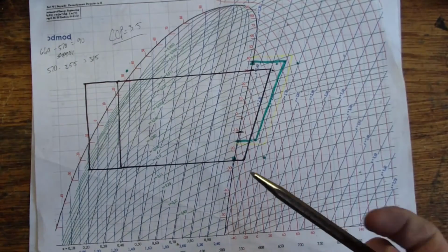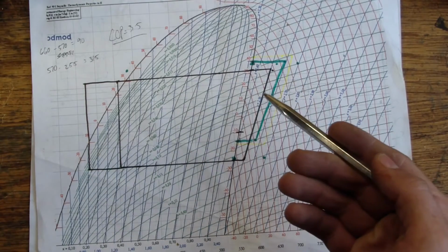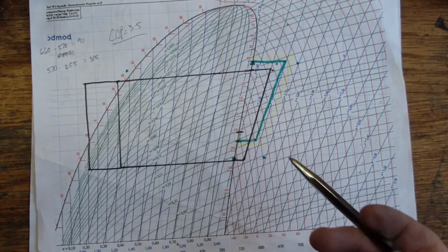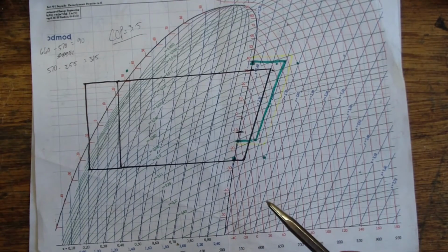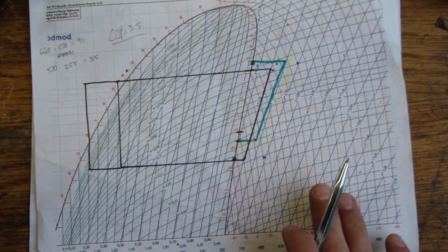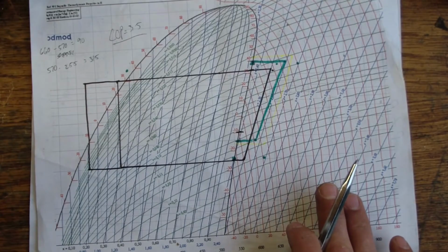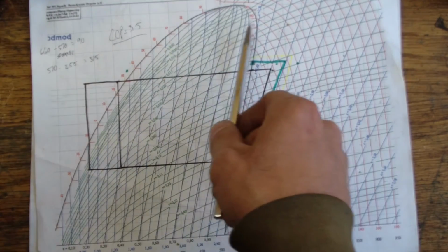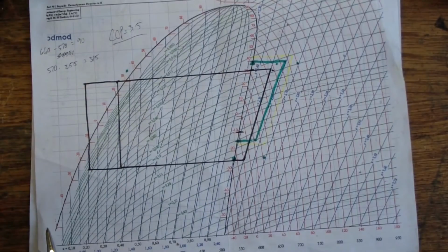But we're going to say that, for our particular application, say this is a refrigerator or a freezer, so I'm operating down here in this region. Now, let's say that this was going to be a high temperature heat pump, and let's say it was going to operate up in the 90s or 100 or 110 degrees Fahrenheit, so really quite warm. We would be operating way up here in the top of this horn. Well, you can see that the width of the horn towards the top is much narrower than the width of the horn towards the bottom here.